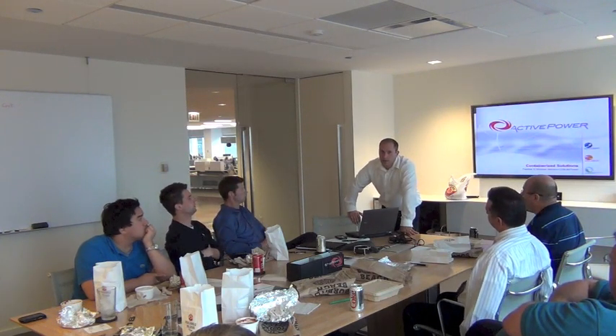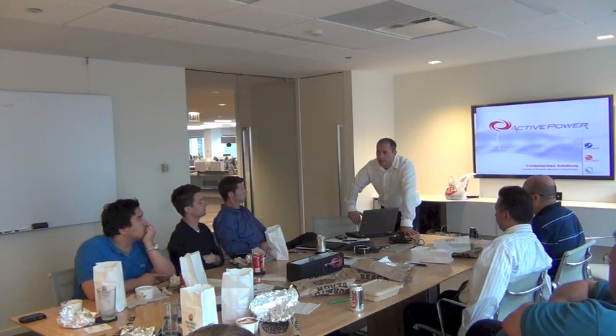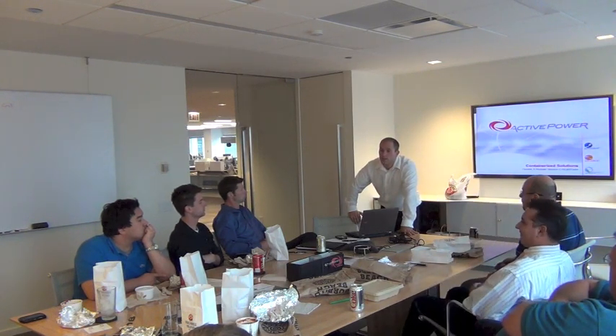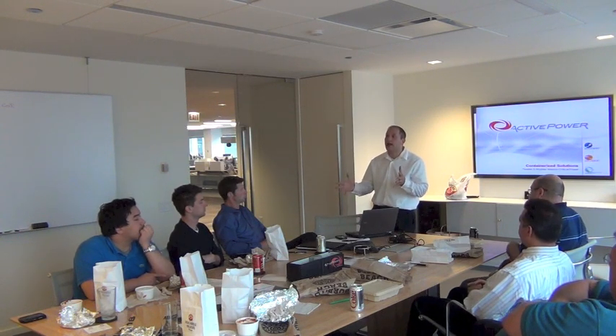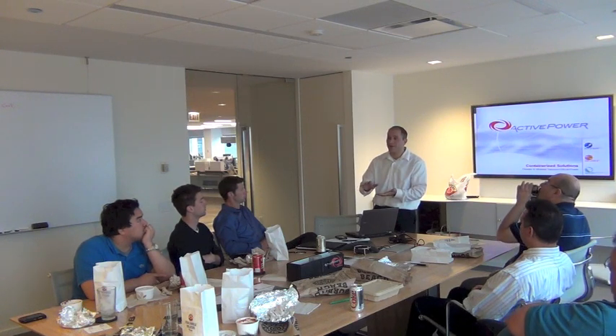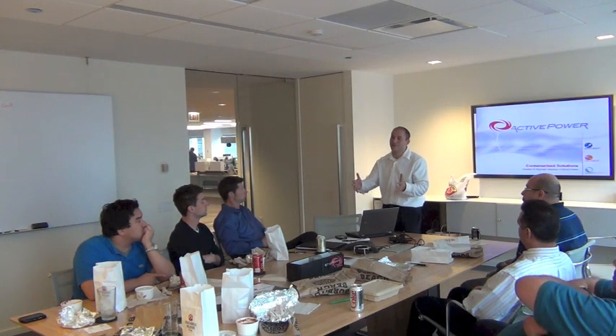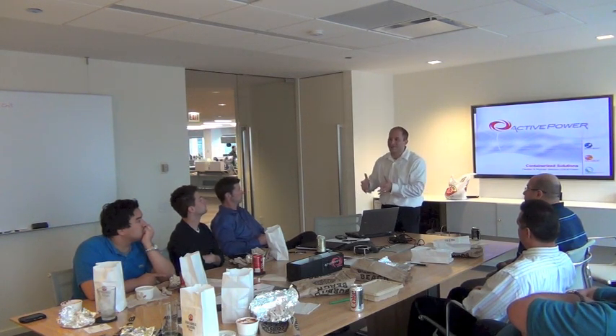I mean, we team up with Caterpillar, Cummins, all the major generator manufacturers have good speed control on their generators. And one of the nice things with our UPS is it's designed to be able to get the load on the generator fast. Some traditional UPSs, what we've seen out there, have firmware where they may even have like a 4-second delay before they even start walking on the load. And a lot of times, during commissioning, they're not really necessarily experts about designing around what's the difference between this UPS and batteries and this UPS and using flywheels.